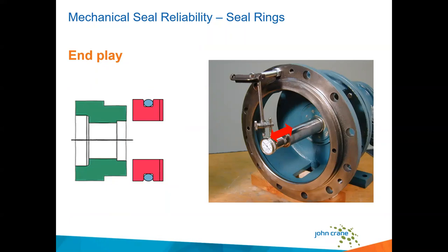So this is a little bit of an exaggerated example, but that's in essence what you'd be looking at if you have a lot of play in your shaft. You really shouldn't have any more than, considering a typical ball type thrust bearing, 5 thousandths total, probably less than that. Obviously, if you had a tilt pad style bearing, you're going to have more potential play in the shaft.